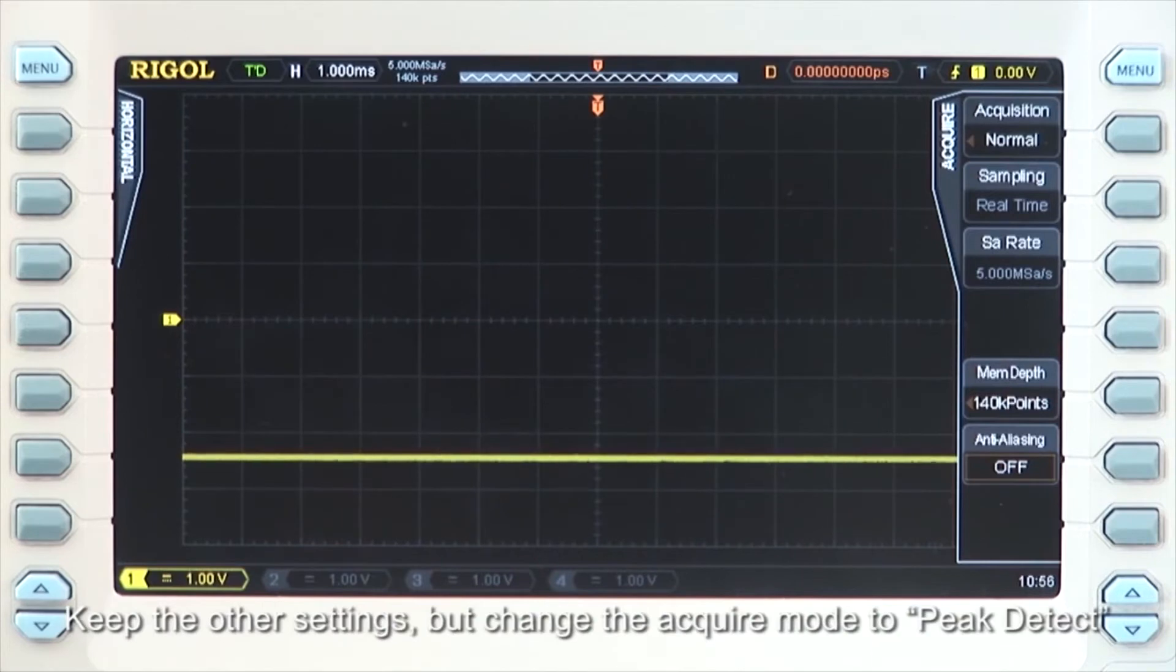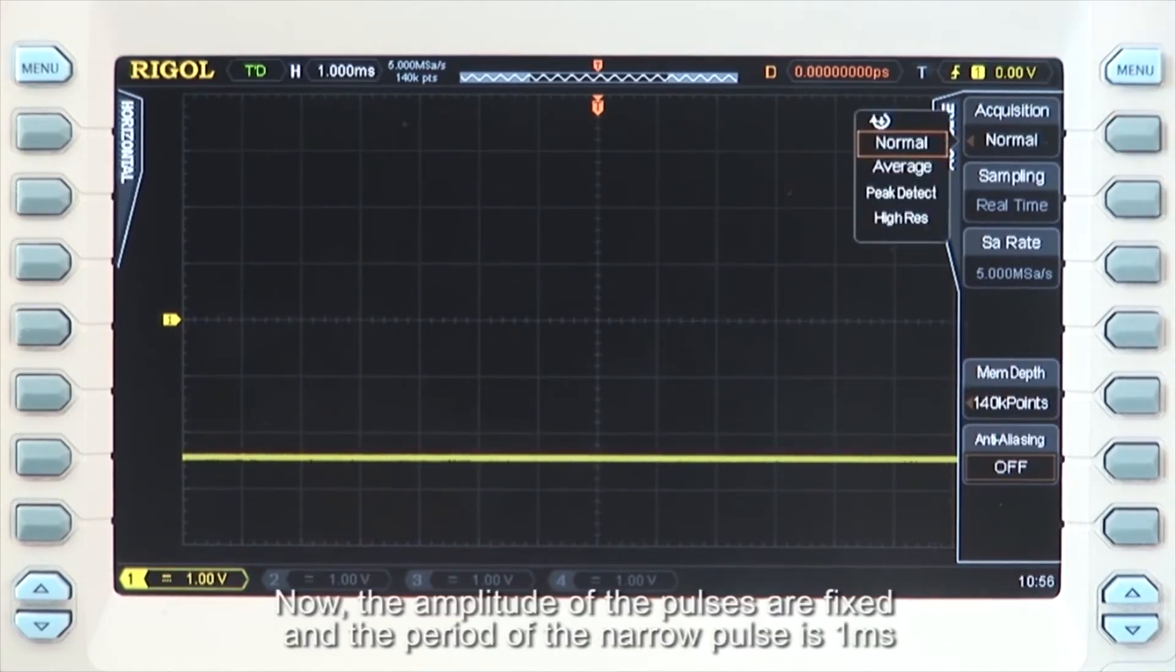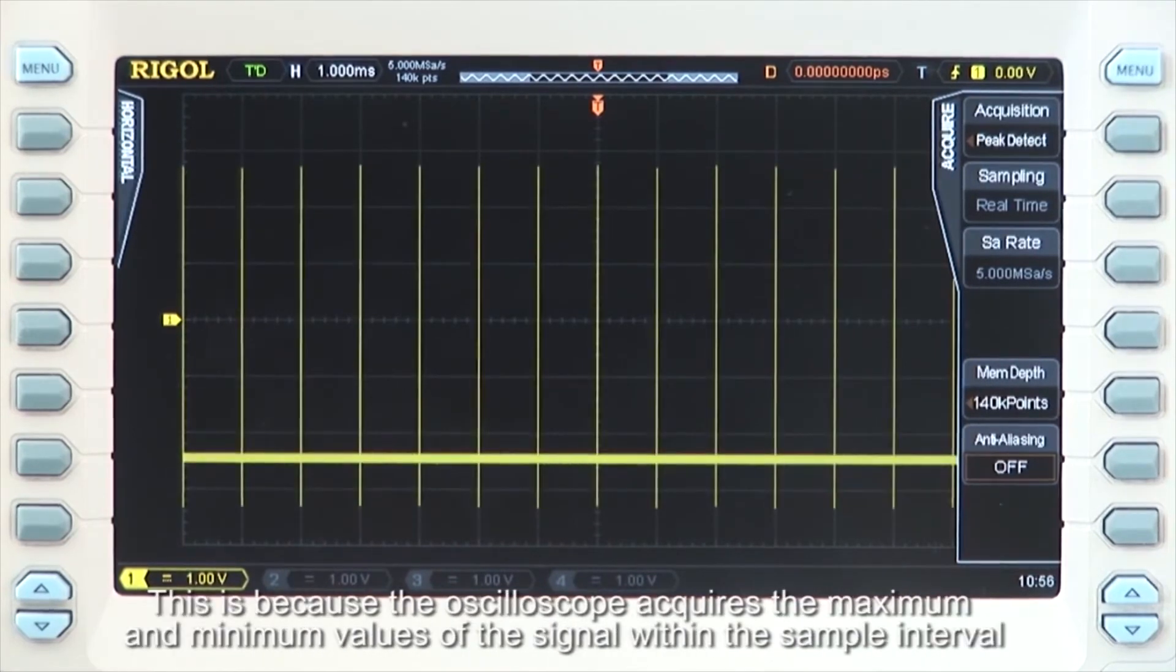Keep the other settings but change the acquire mode to peak detect. Now the amplitude of the pulses are fixed and the period of the narrow pulse is 1 millisecond. This is because the oscilloscope acquires the maximum and minimum values of the signal within the sample interval.